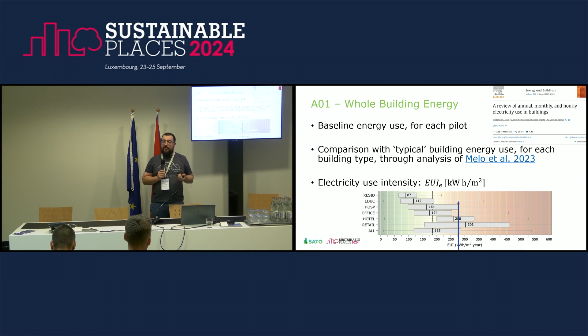We measure the average illuminance, which for an office or educational type building we want to be about 500 lux. So we fulfill that average illuminance check KPI, but we don't want one place to have 1,000 lux and another to have 0, which would fulfill the average but wouldn't be a very good system. So we also look at uniformity, which is pretty much the ratio between the worst point and the average, and you want that to be above 60%.